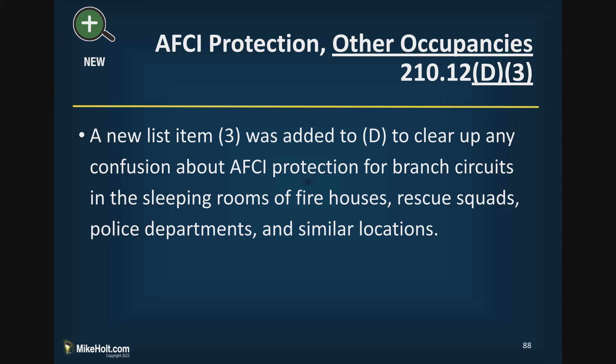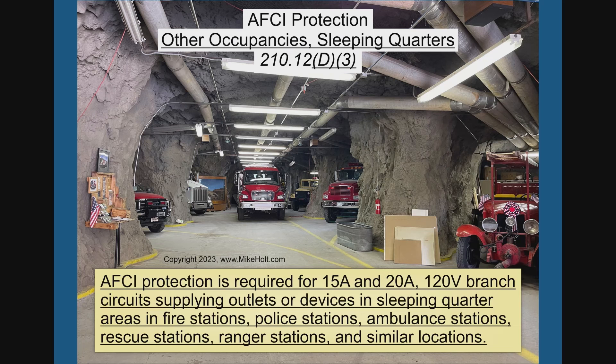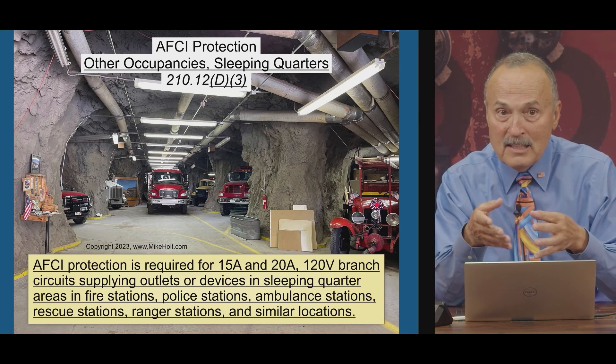A new item D3 was added to clarify AFCI protection requirements for branch circuits in sleeping rooms of fire houses, rescue squads, police departments, and similar locations. Visiting a fire station in Creed, Colorado, I saw one of these facilities. The firefighters there indicated they don't actually have a sleeping area, so in reality it would only be the bedroom spaces in firehouses that require AFCI — not the whole building.